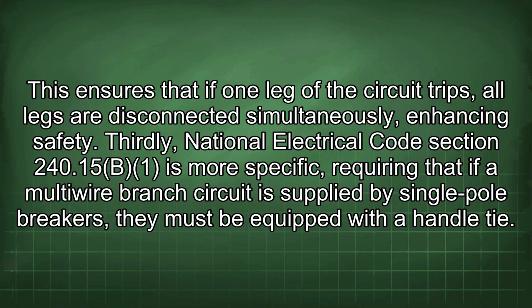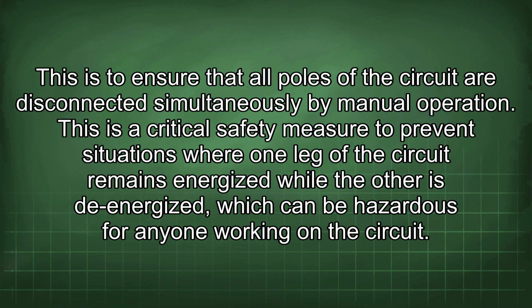Thirdly, National Electrical Code Section 240.15(B)(1) is more specific, requiring that if a multi-wire branch circuit is supplied by single-pole breakers, they must be equipped with a handle tie. This is to ensure that all poles of the circuit are disconnected simultaneously by manual operation. This is a critical safety measure to prevent situations where one leg of the circuit remains energized while the other is de-energized, which can be hazardous for anyone working on the circuit.